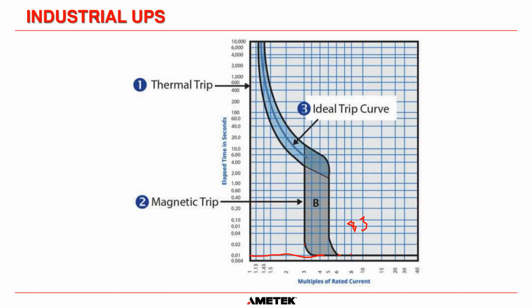Okay, so it's going to trip that breaker pretty much instantaneously, and therefore all of the other loads connected to the system are not going to see a disruption in the time that it takes for that three-phase system to actually trip that breaker. Because remember, if you have a short on one system, the only way the inverter can handle that is it will try and reduce its output voltage to limit the current into that fault. And in doing so, reducing its voltage could disrupt some of the other loads on that circuit. In truth, it should trip to bypass and then clear the fault that way. But you would much rather the inverter tripped it without tripping to bypass if necessary.